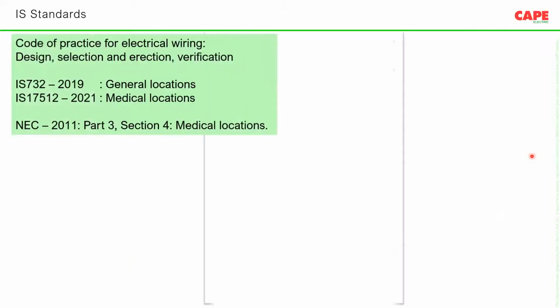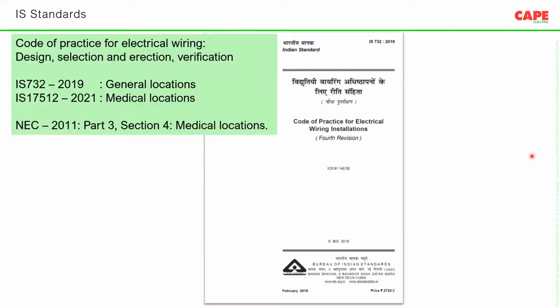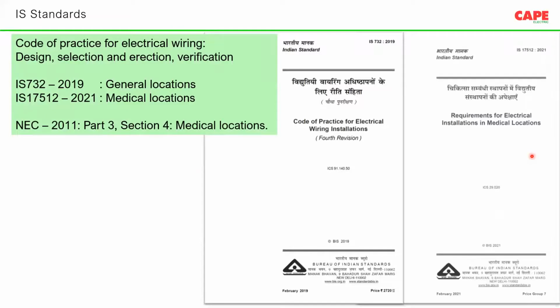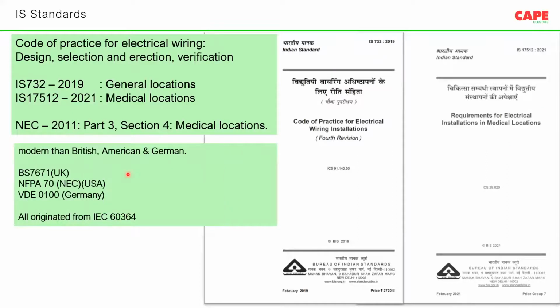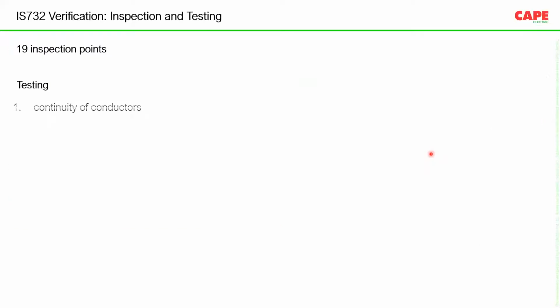Now about the IS standard on medical location. For medical location or for hospitals, there are two standards applicable: IS 732 Code of Practice of Electrical Wiring and IS 17512, which is exclusively for medical location. Don't think that the second one is applicable for the whole hospital. No, the second one is applicable only for the medical location. Medical location is the place where a patient is connected to biomedical equipment. Only that particular place this standard is applicable. And this standard, with respect to American, German, British, French and other standards, our standard is equally good because this is adopted from the most modern IEC standards.